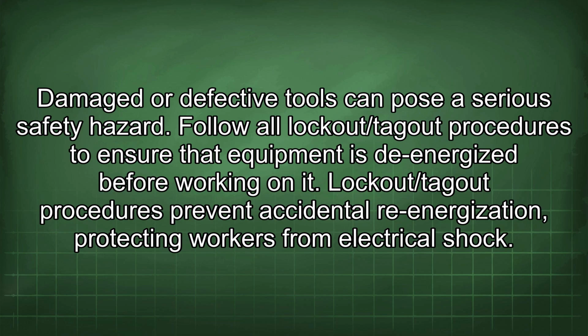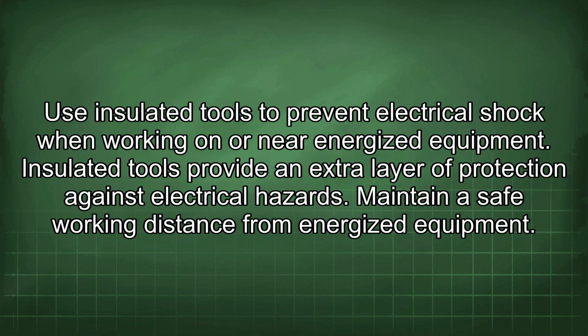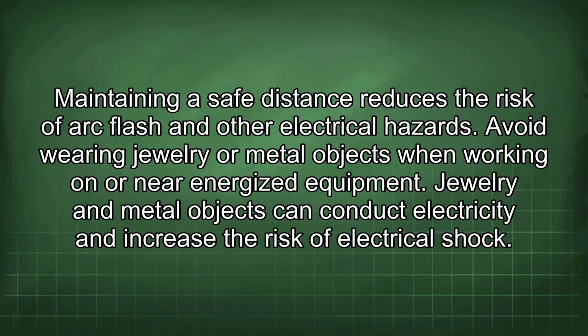Follow all lockout/tagout procedures to ensure that equipment is de-energized before working on it. Lockout/tagout procedures prevent accidental re-energization, protecting workers from electrical shock. Use insulated tools to prevent electrical shock when working on or near energized equipment. Insulated tools provide an extra layer of protection against electrical hazards. Maintain a safe working distance from energized equipment. Maintaining a safe distance reduces the risk of arc flash and other electrical hazards.